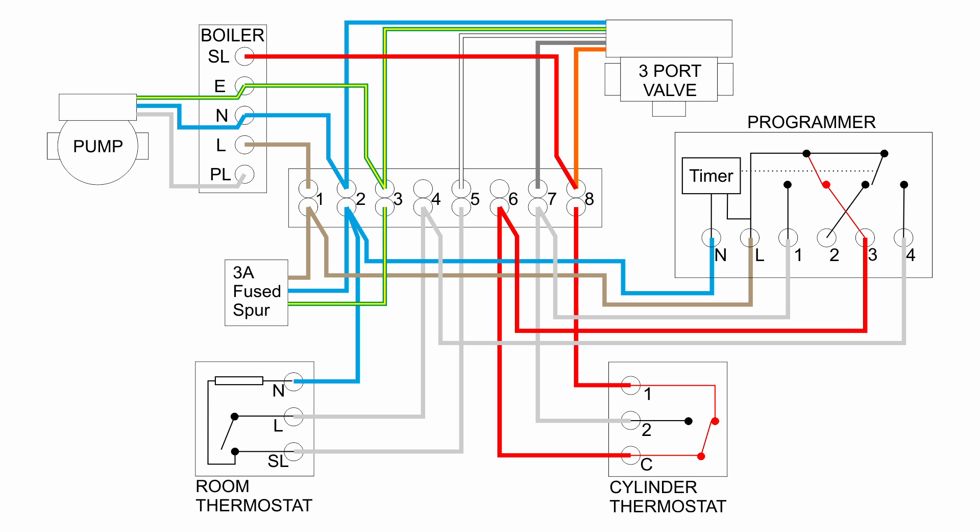The valve of course is not actually involved at all, and although there is the orange wire connected there, which of course will come live there. The orange wire is actually a switched output from the valve, so the connection that's live doesn't do anything with the valve at all, so it will just sit there and pretty much do nothing.